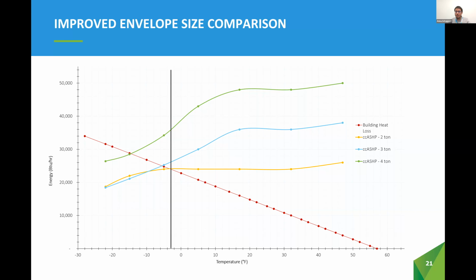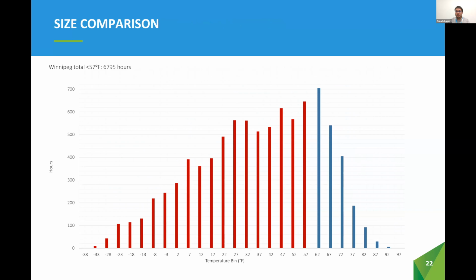The balance point of each unit is as follows as well. The 2 ton comes in at -3 degrees Fahrenheit or -19 Celsius. The 3 ton at -5 degrees Fahrenheit or -20 Celsius, and the 4 ton at -15 Fahrenheit or -26 Celsius. It is interesting to note that for this particular manufacturer, and in this case, the 2 ton unit essentially meets the same heating output demands of the building as the 3 ton unit. So the 2 ton unit meets roughly the same hourly profile as the 4 ton unit in the previous example.